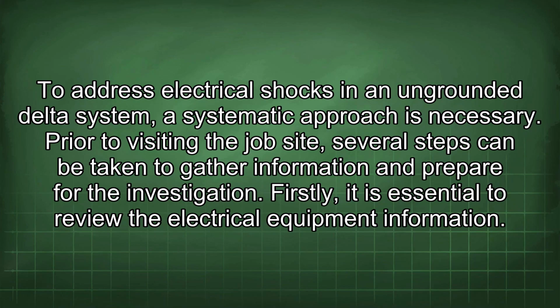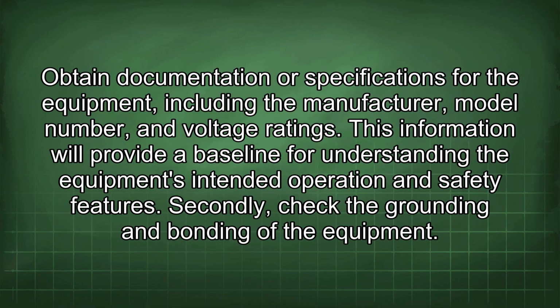To address electrical shocks in an ungrounded delta system, a systematic approach is necessary. Prior to visiting the job site, several steps can be taken to gather information and prepare for the investigation. Firstly, it is essential to review the electrical equipment information. Obtain documentation or specifications for the equipment, including the manufacturer, model number, and voltage rating. This information will provide a baseline for understanding the equipment's intended operation and safety features.